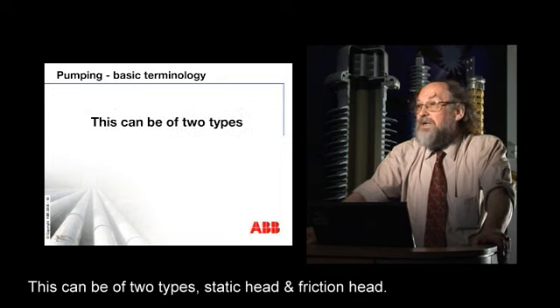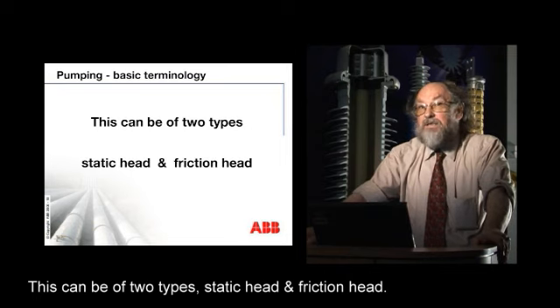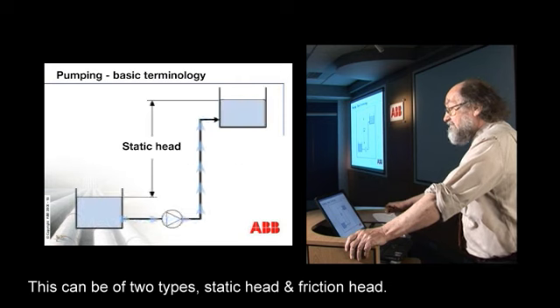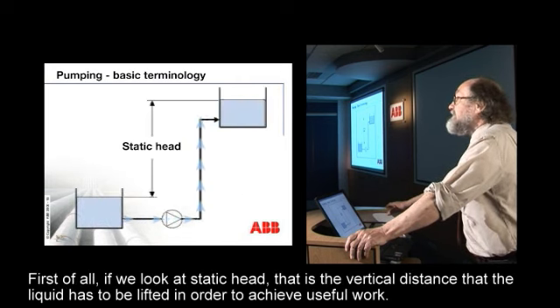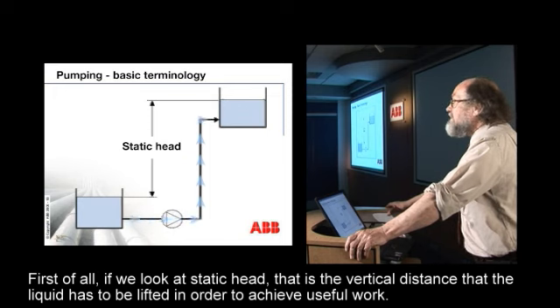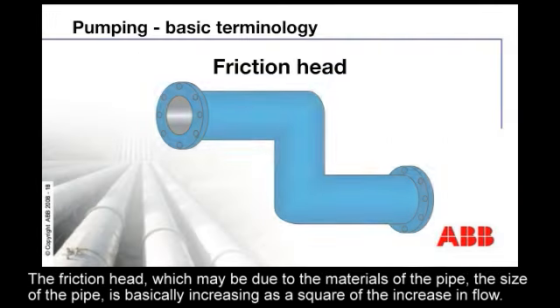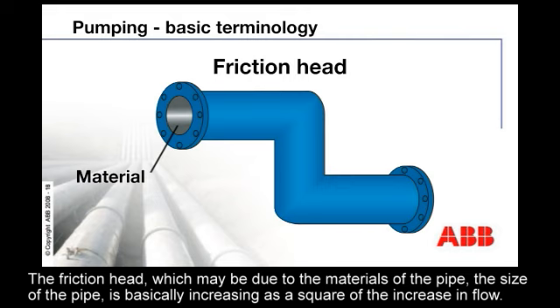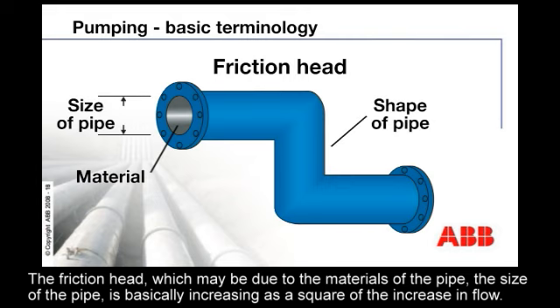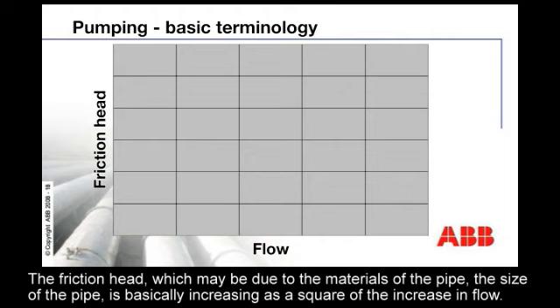This can be of two types: the static head and the friction head. The static head is the vertical distance that the liquid has to be lifted in order to achieve useful work. The friction head, which may be due to the materials of the pipe or the size of the pipe, increases as a square of the increase in flow.